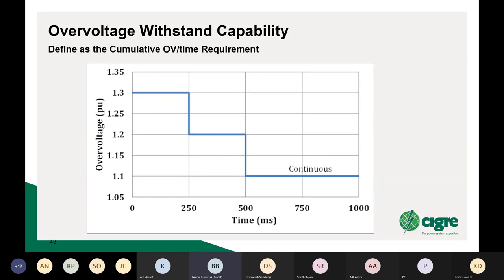Similarly with over-voltage withstand capability, this is a typical requirement. So overvoltage of 1.3 for 250, 1.2 for 500, etc. And typically these requirements are there because you want the equipment to ride through events that can happen following a loss of a single pole, and you may get some severe overvoltages, and you want the other pole to ride through that. And so this is an important part of the specification.